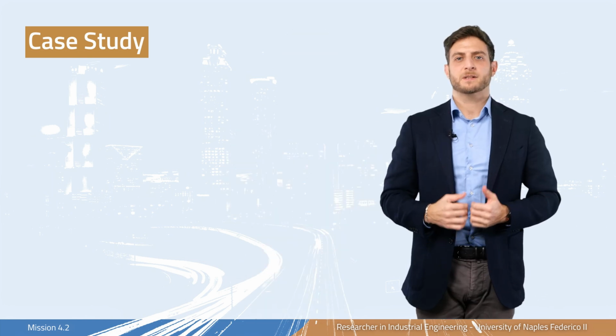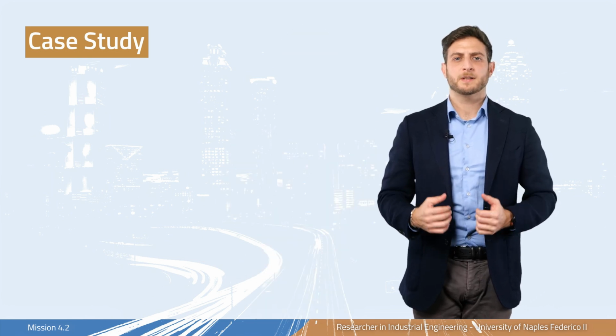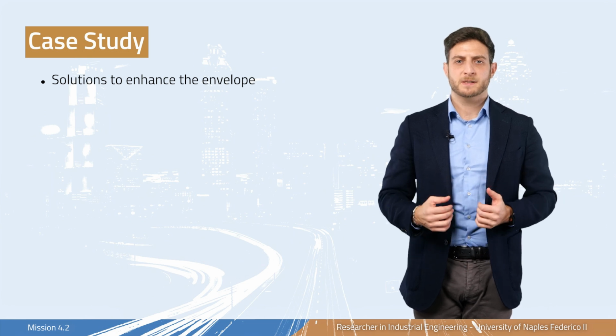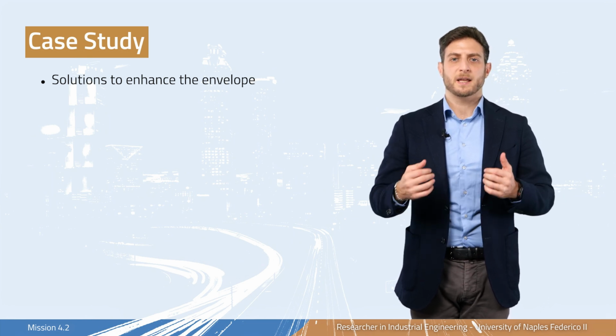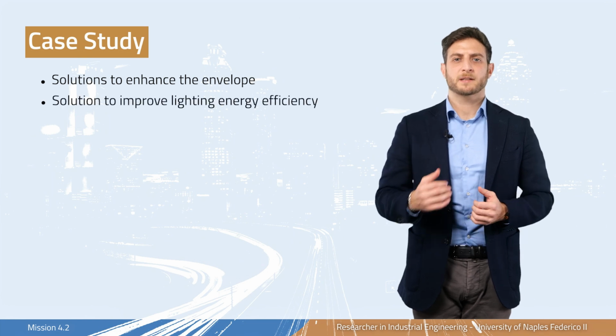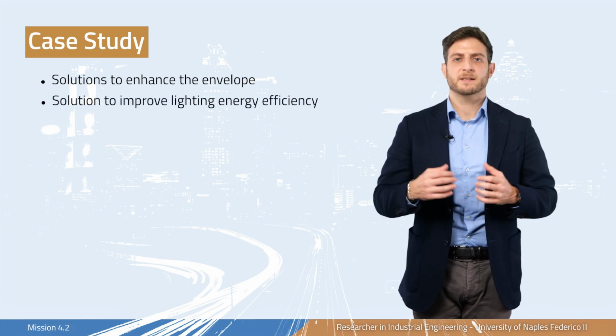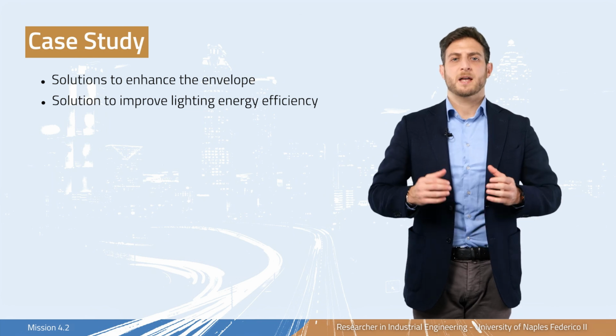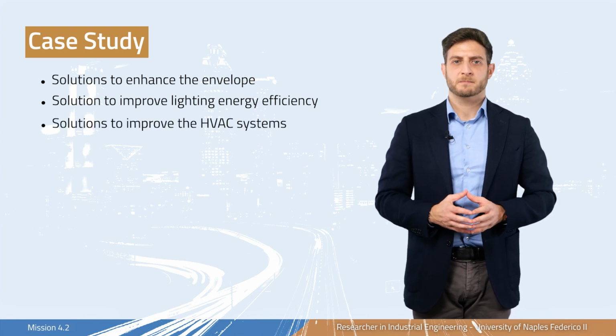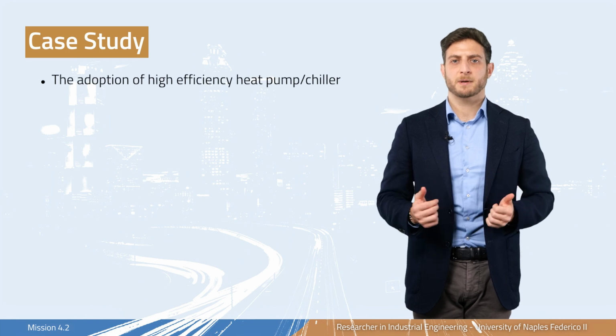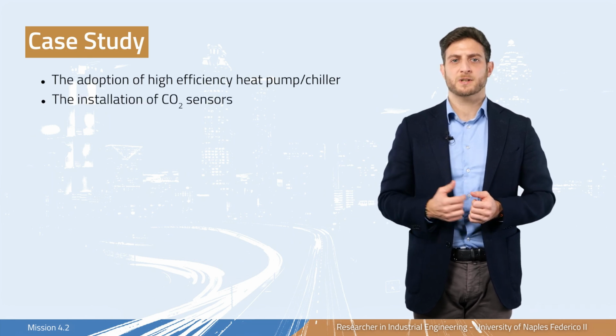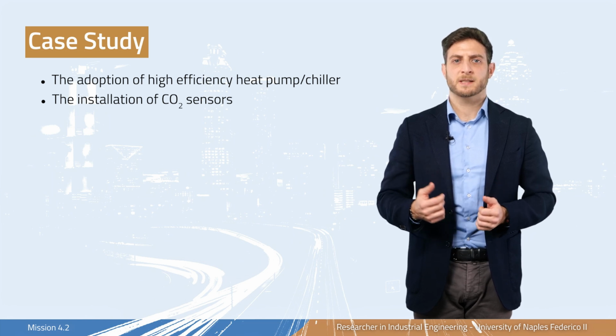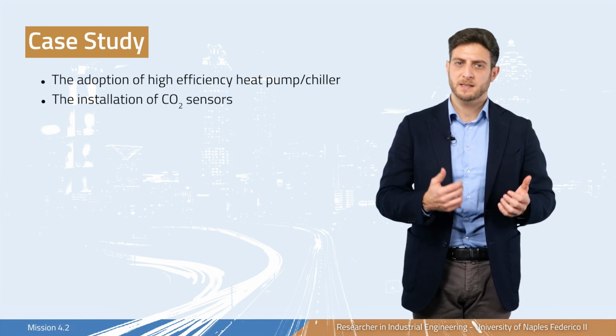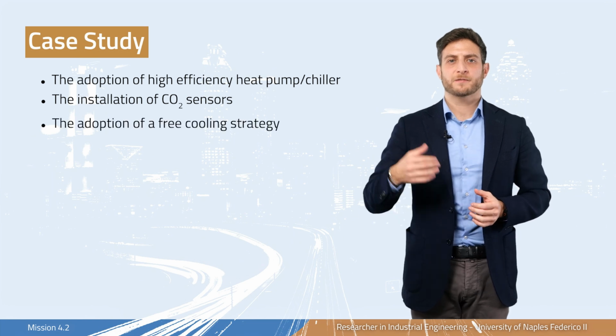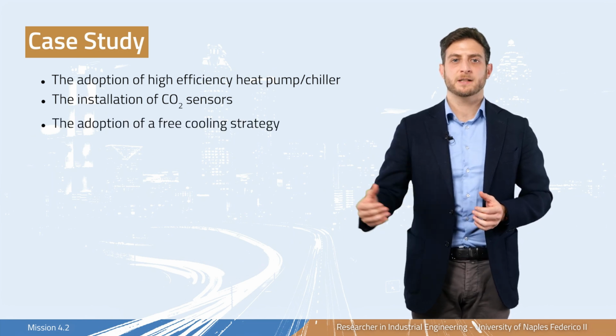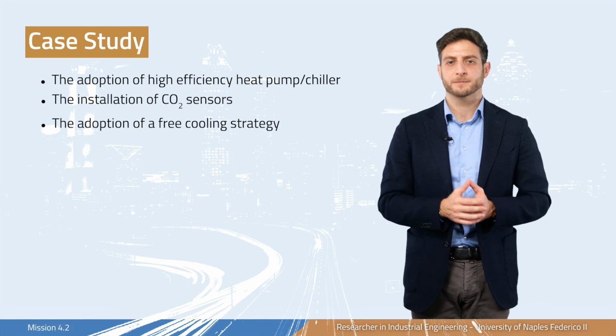The specific energy efficiency measures investigated can be grouped into: solutions to enhance the envelope, such as upgrading existing single glazing and thermal insulation; solutions to improve lighting, such as replacing existing lights with LED ones; and solutions to improve HVAC systems, such as adopting high-efficiency heat pump chillers, installing CO2 sensors to adjust ventilation rates based on actual occupancy and reduce unnecessary heating and cooling energy use, or adopting free cooling strategies that use outside air for cooling when outdoor conditions are favorable.